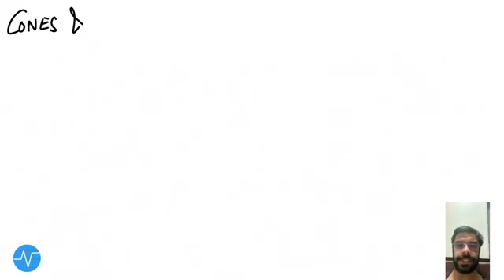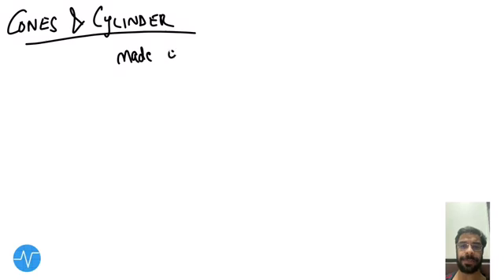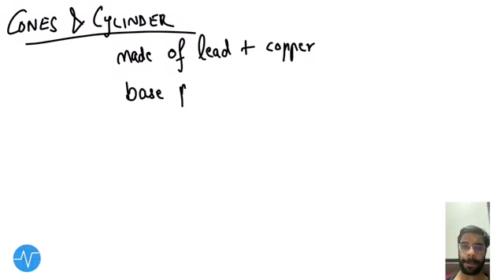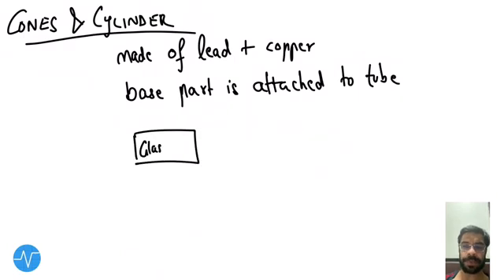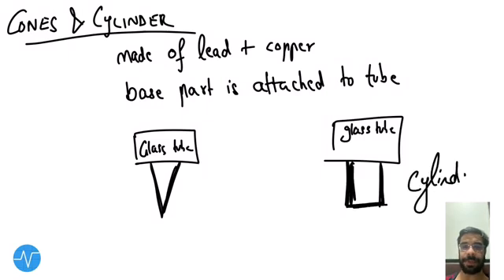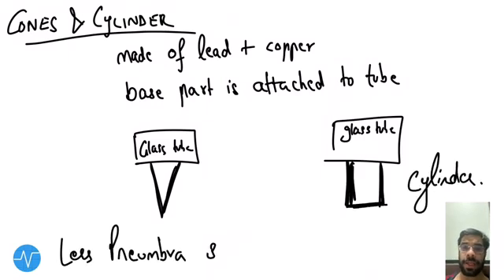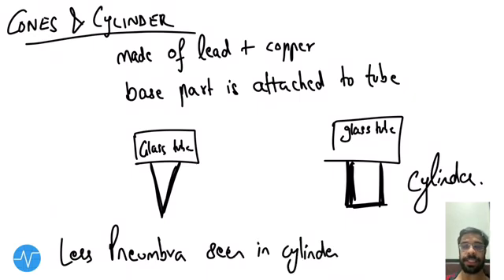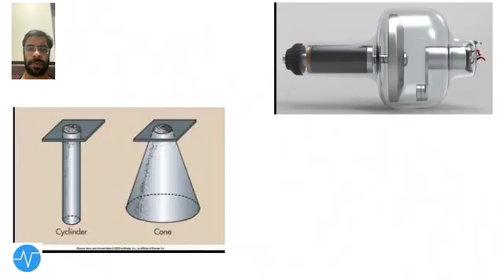The second beam restricting device is cones and cylinders. It is made up of lead and copper. The base part is attached to the x-ray tube. In the diagram, the base part of the cone and the base part of the cylinder are both attached to the tube. There is less penumbra seen with the cylinder compared to the cone.